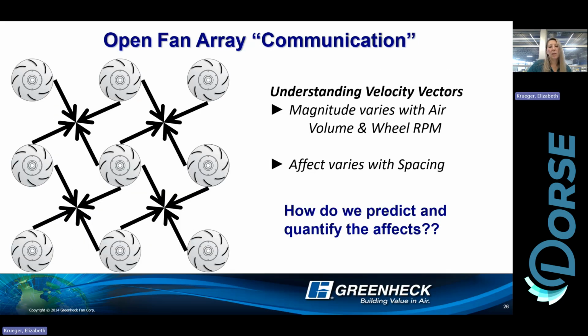Let's take a look at that here. So comparing housed to unhoused, first let's talk about airflow. Fans in an array will have communication. Sometimes I refer to it as translation. There has been no AMCA testing on fan arrays up to this point. So really we're kind of going it alone in the market as far as putting fans in an array and then hoping that what is spec'd out is actually going to produce the air that is being required.